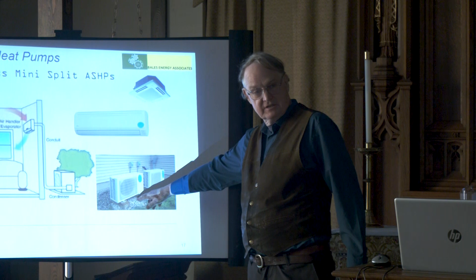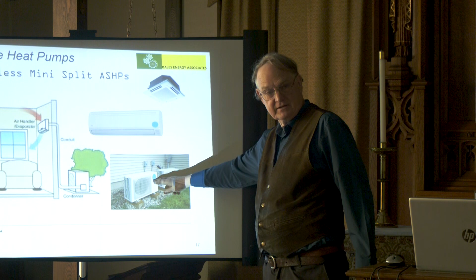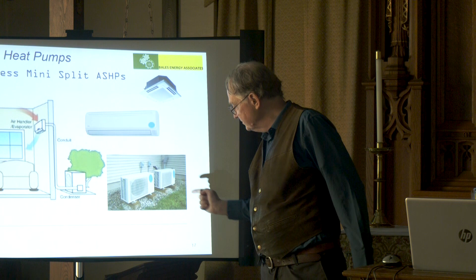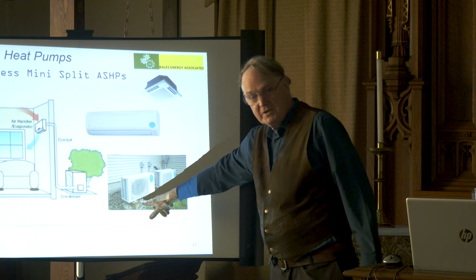Snow tends to fall from the sky. Down south, they don't experience that, so they can put their heat pumps on the ground like this, low. But this should be on a rack, in my opinion, 18 inches off the ground, so it doesn't get buried, because the air is blowing this way. A lot of air conditioning contractors put these on the ground because they're used to doing air conditioners, which don't get covered with snow.